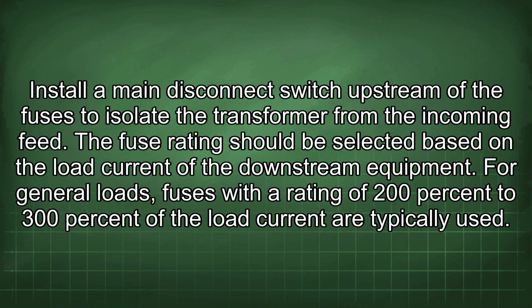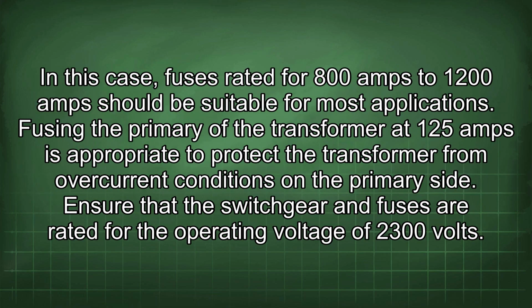The fuse rating should be selected based on the load current of the downstream equipment. For general loads, fuses with a rating of 200% to 300% of the load current are typically used. In this case, fuses rated for 800 amps to 1200 amps should be suitable for most applications. Fusing the primary of the transformer at 125 amps is appropriate to protect the transformer from overcurrent conditions on the primary side. Ensure that the switchgear and fuses are rated for the operating voltage of 2300 volts.